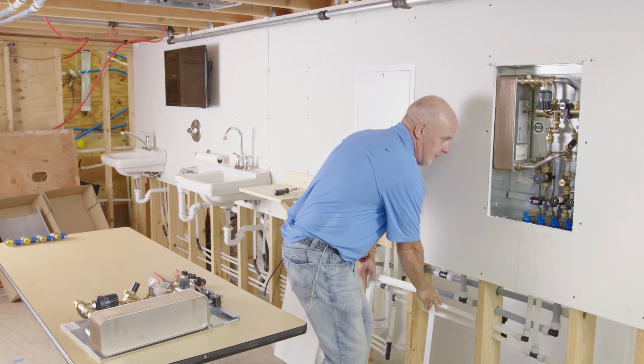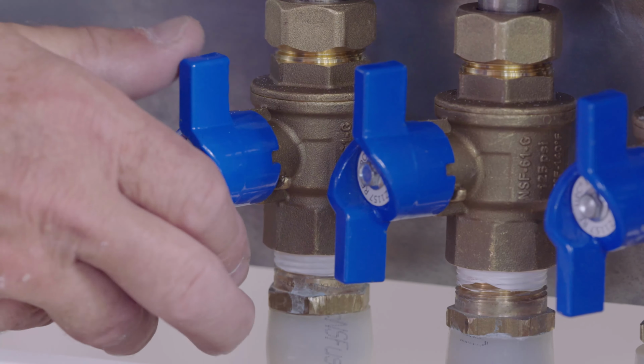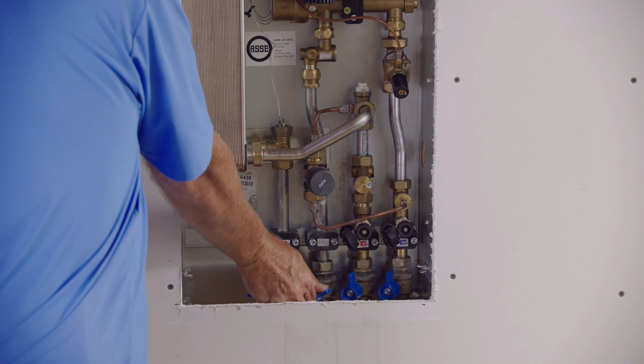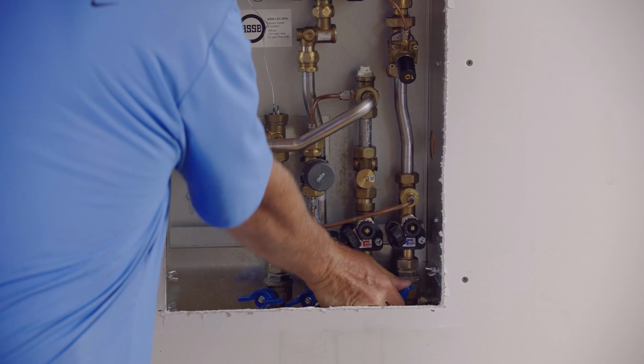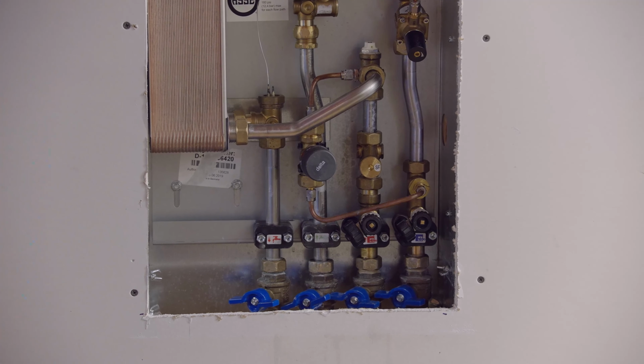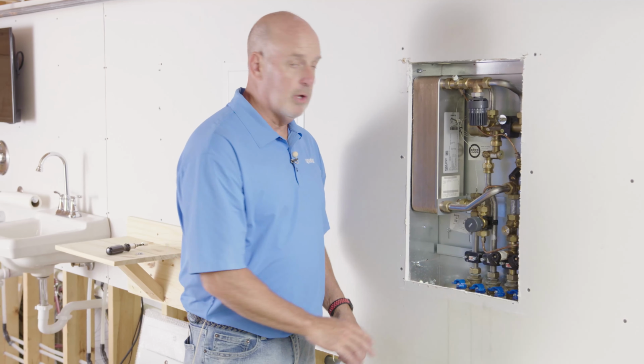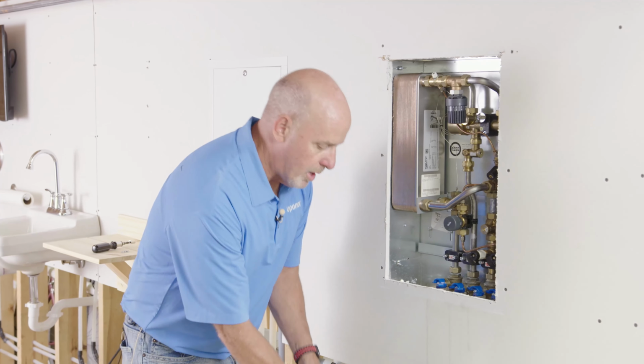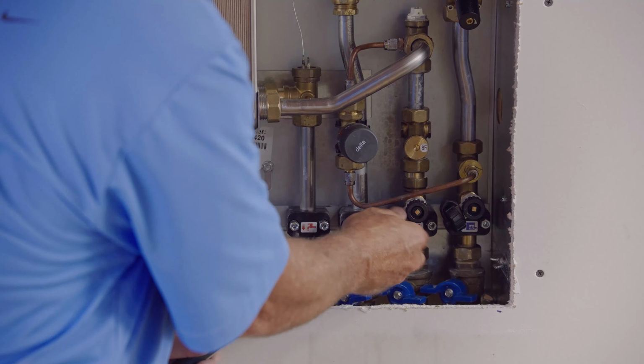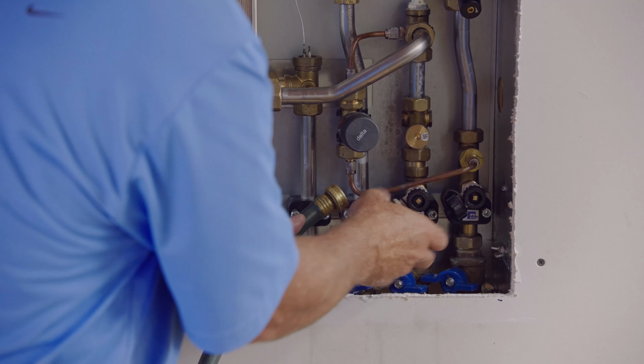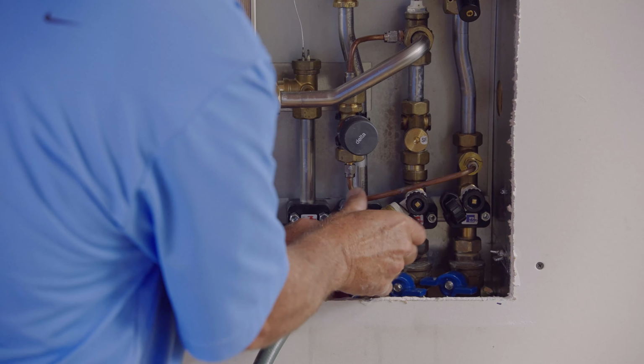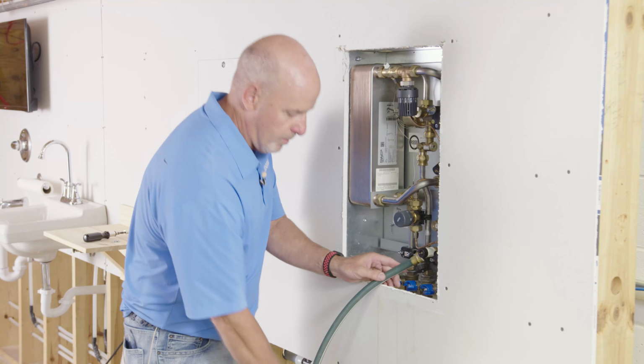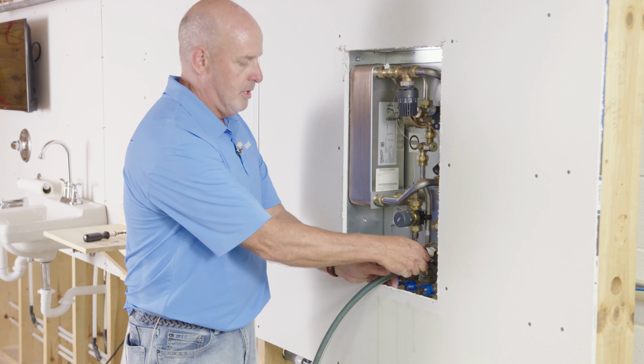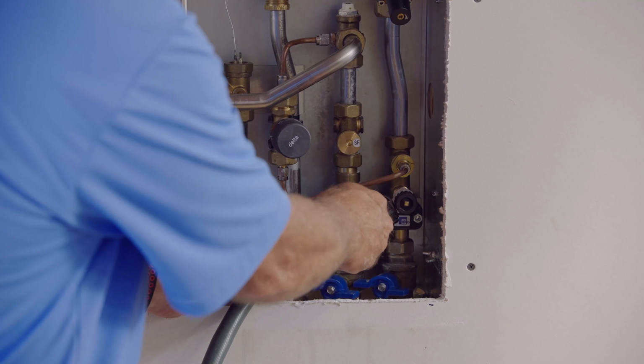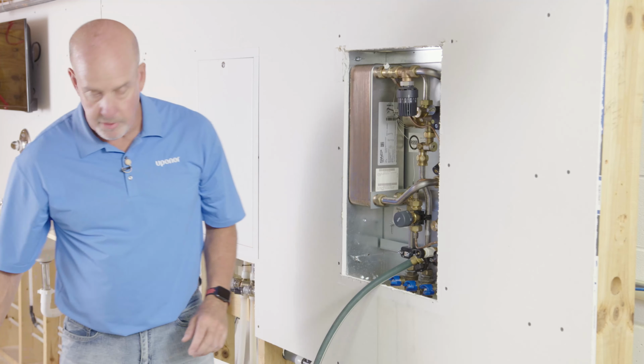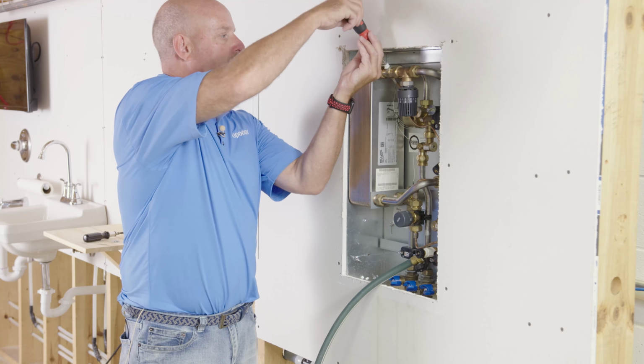Set that aside. Next thing we'll do is we'll shut the valves. Now that we've got the valves closed, the next step is to drain the water from the unit on the heating side. We'll remove the cap, attach our drain hose, drop the other end into a bucket or a suitable drain, and then open up the valve. You can also aid the draining process by opening up the air vent on the top of the heat exchanger.